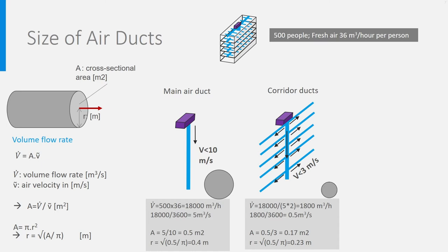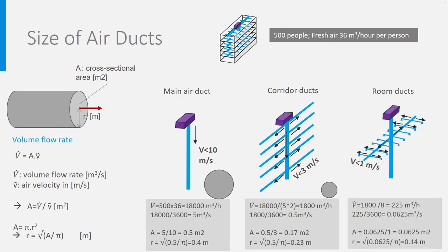Finally, the ducts to the rooms. If we assume that there are four branches at each side, at both sides of the corridor, eight branches per half floor therefore, then each room duct should convey 1,800 divided by 8 equals 225 cubic meters per hour, which is 0.0625 cubic meter per second. With a maximum air velocity of 1 meter per second, this leads to a cross-sectional area of 0.0625 square meter, corresponding to a radius of 14 centimeter, which is 28 centimeter diameter. So, it is not that complicated to find out the size of piping.